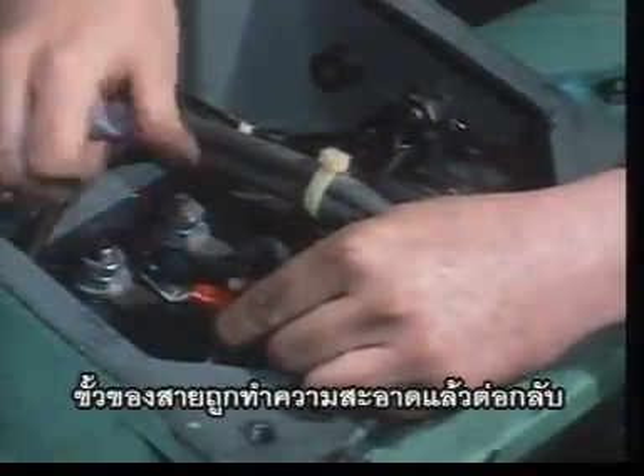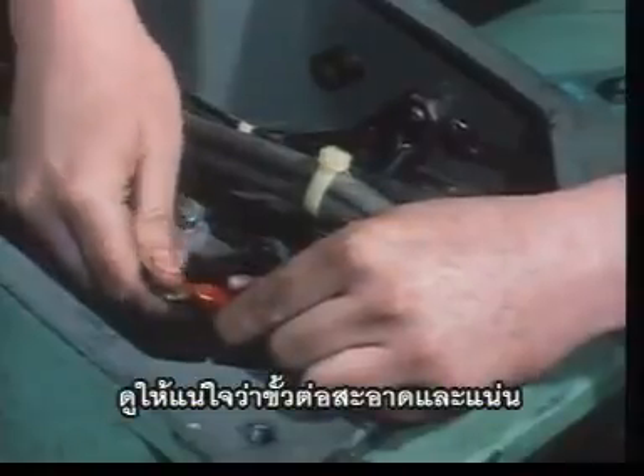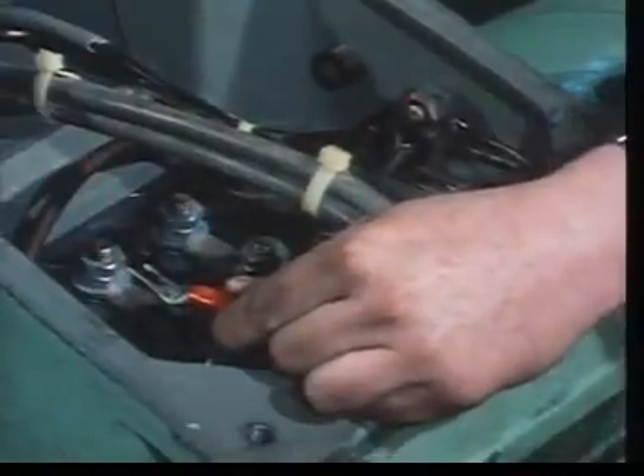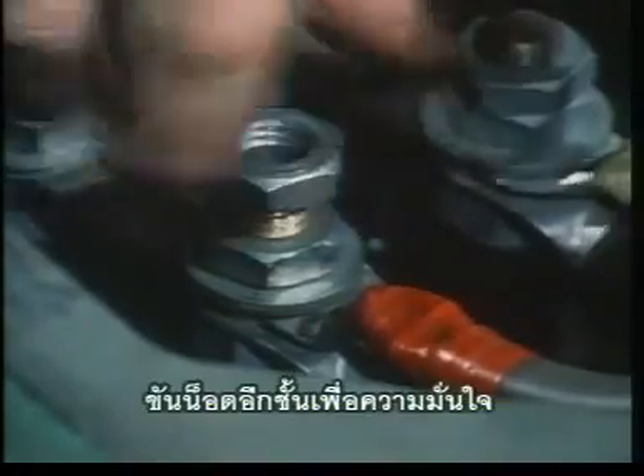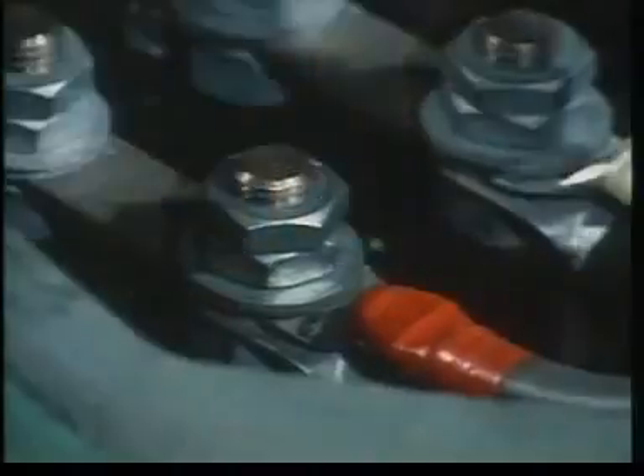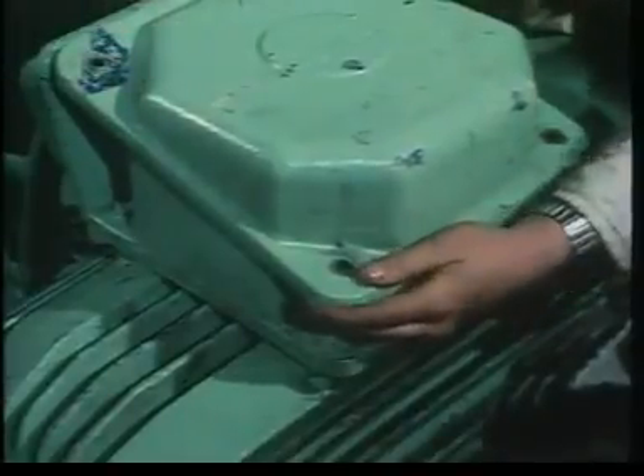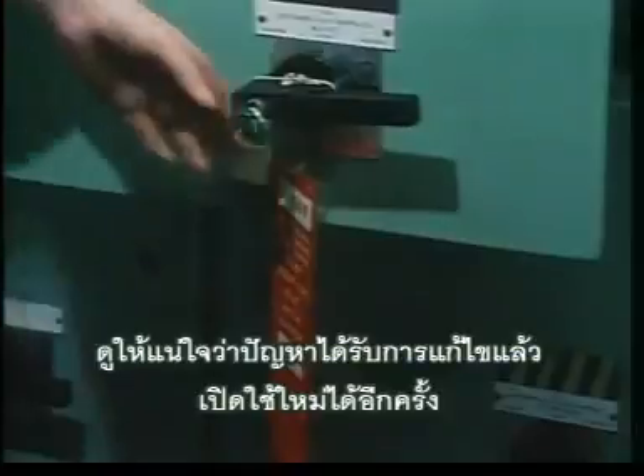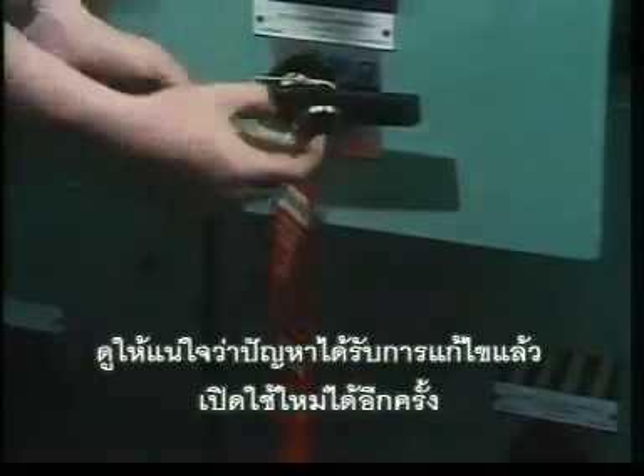Now the cable lug is cleaned and the connection is remade, making sure that the connection is clean and tight. Here, a lock nut secures the connection. Having checked that the fault has been eliminated, the service can be reinstated.